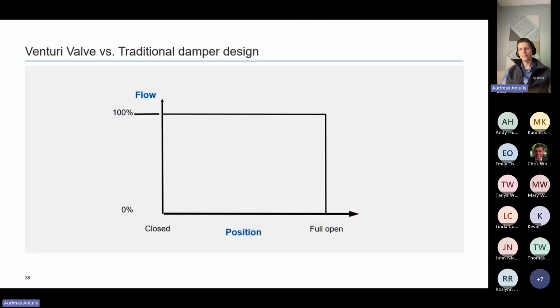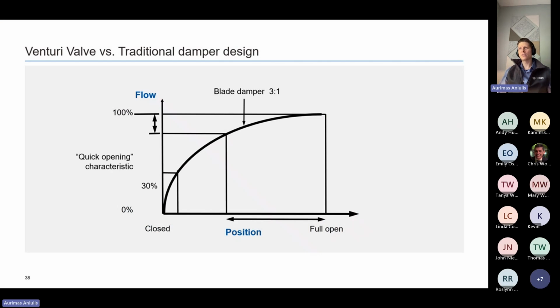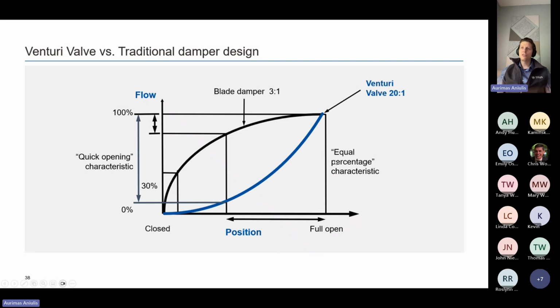Performance highlights of the Venturi air valves. When we look at the flow, blade style valves have this inherent feature where just as you crack it open, there's a little back pressure built up. So you get a surge of CFM coming out of it from about 0 to 10% open. Whereas with the Venturis, it's the opposite. On the lower end, we have this very nice gradual control that really gives us stable airflow metering capabilities. At the low end with the blade style valve, that's still a challenge, and various valves on the market are working to get around this phenomenon. So that's the advantage of the Venturi, especially when it comes to these low-end controls for vivariums, where you need very low flows for multiple small animal containments.